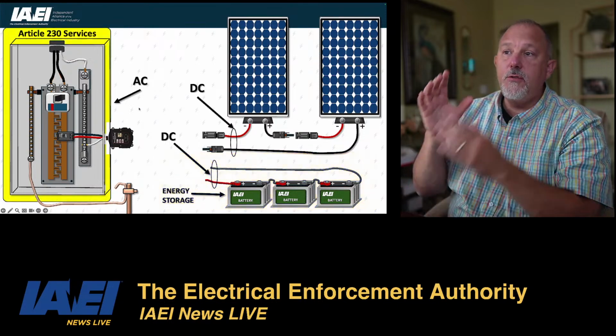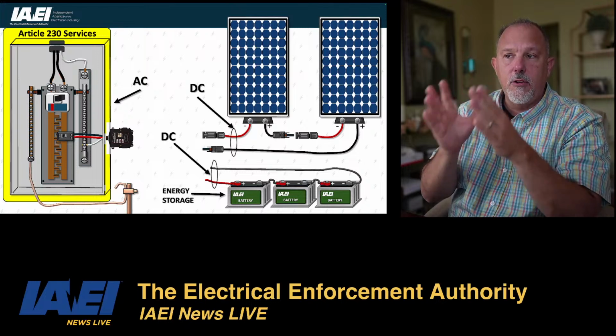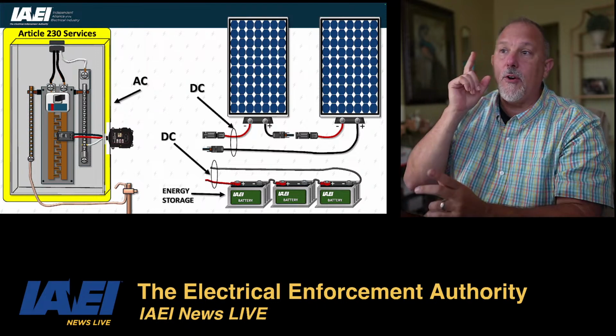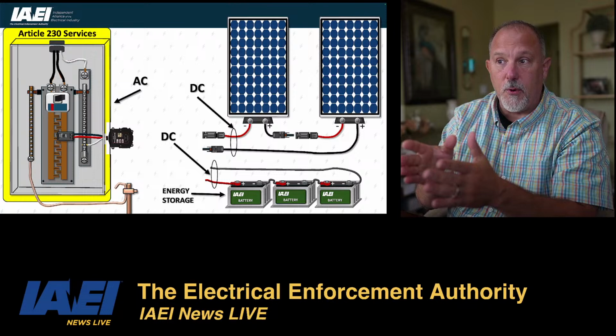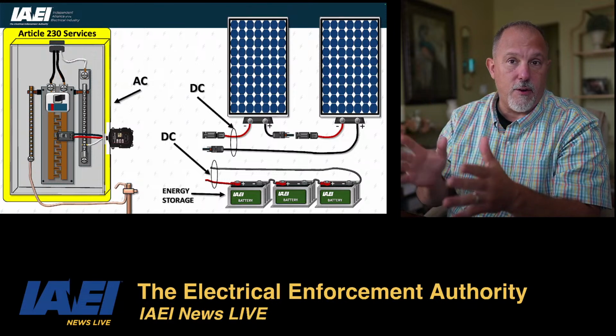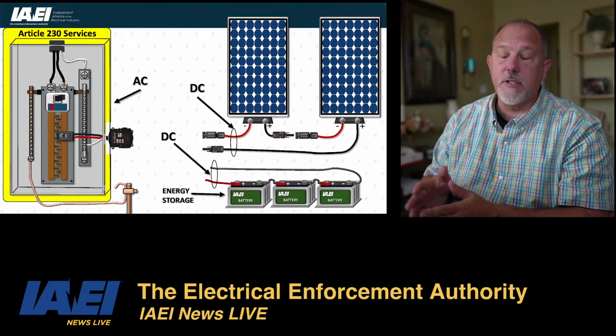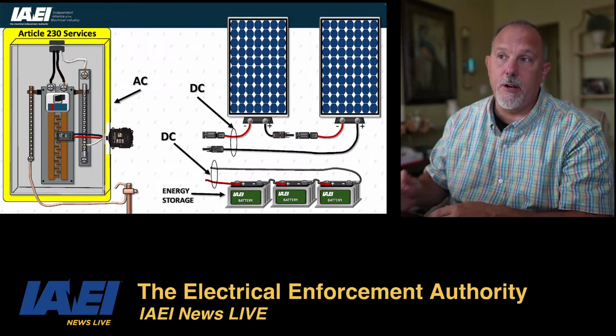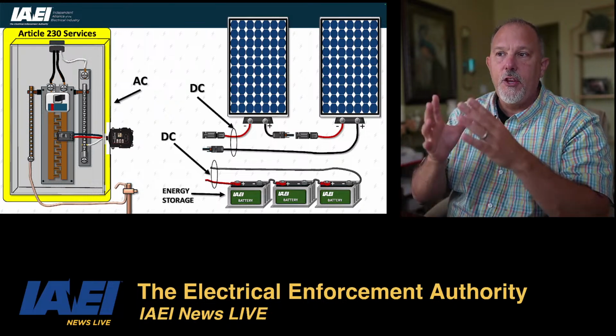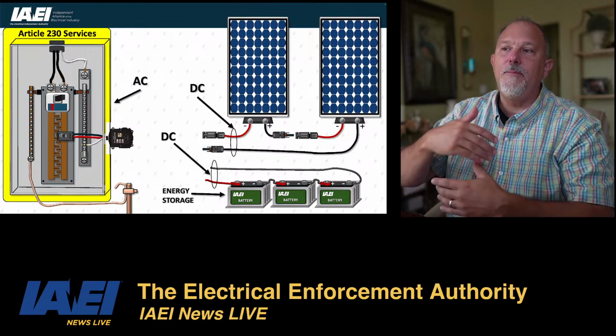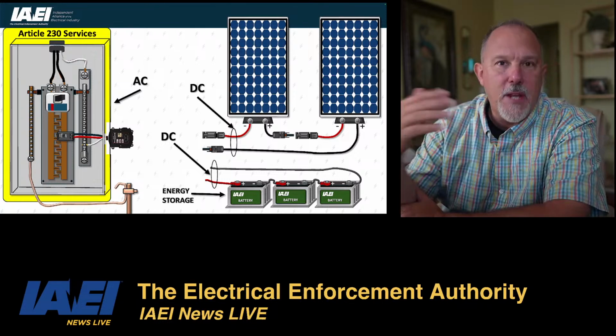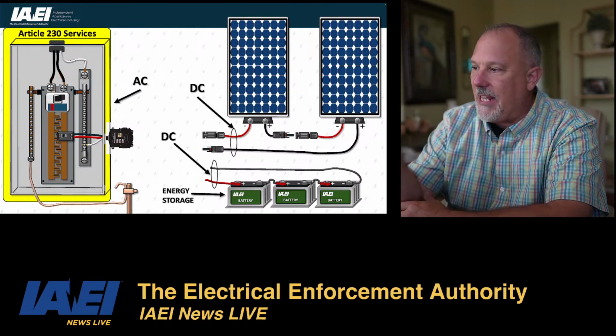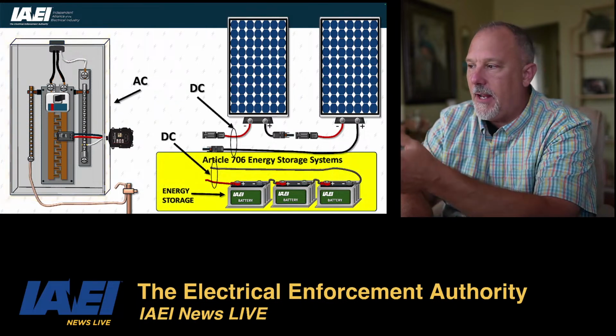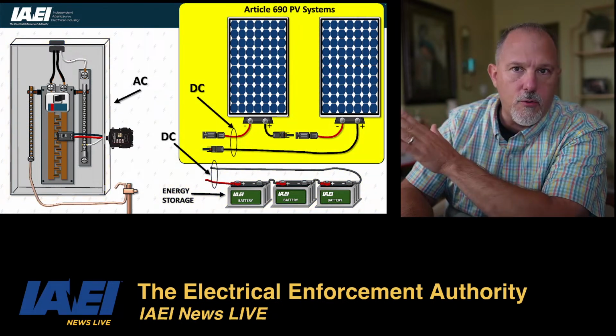In addition to services, right? So we've got to look at services in Article 230. And I would argue that since that's a panel board in the picture that I'm drawing, Article 408 would apply, whether it's a panel board, switchboard, or switchgear, your service equipment. You have Article 230, but then you can't forget that there are other items within each of these, whether it be an energy storage system or an Article 690 system.